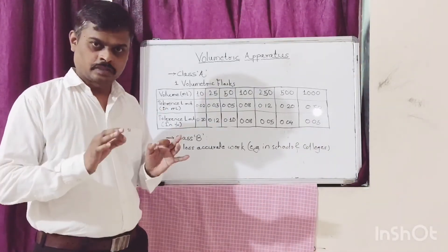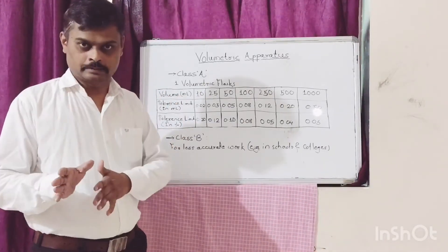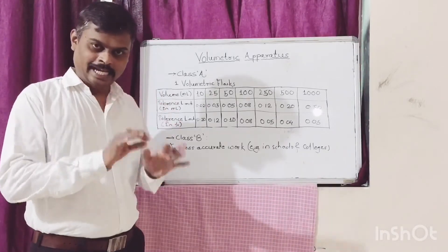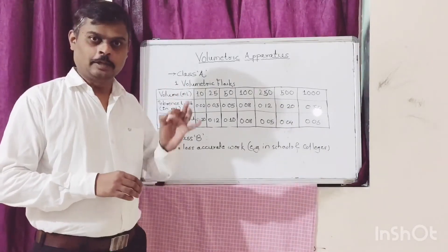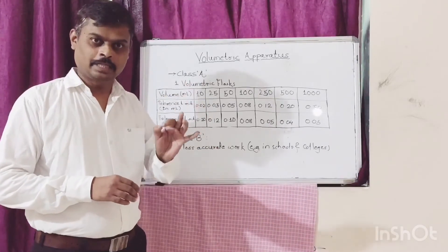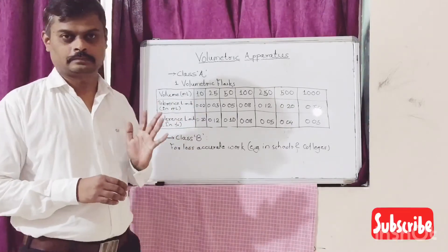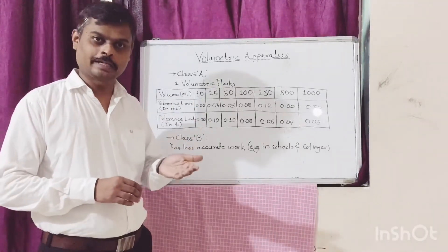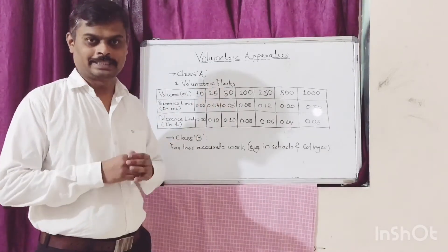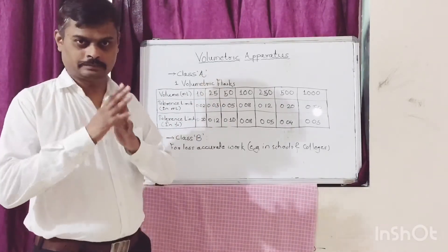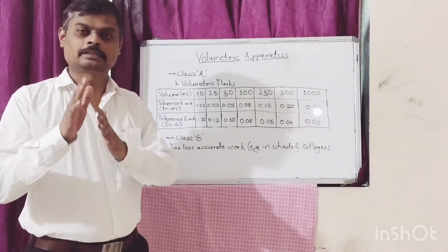If your expected burette reading is less than 10 ml, it is mandatory to use a burette of 10 ml or a micro burette of 10 ml. You cannot use a burette of 25 ml or 50 ml. This is mentioned in USP General Chapter 31.